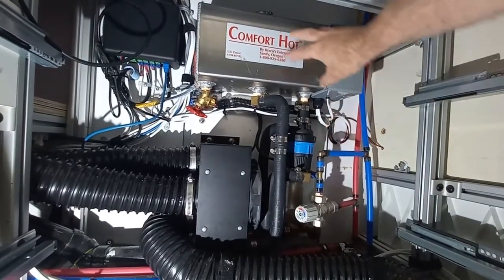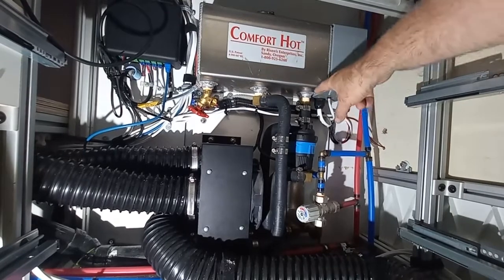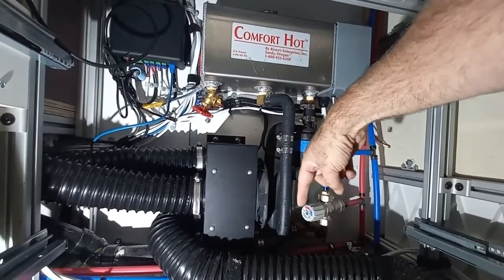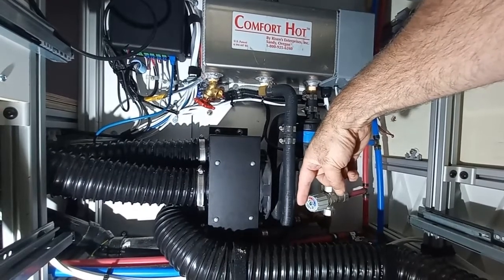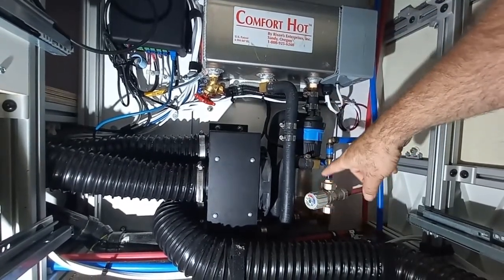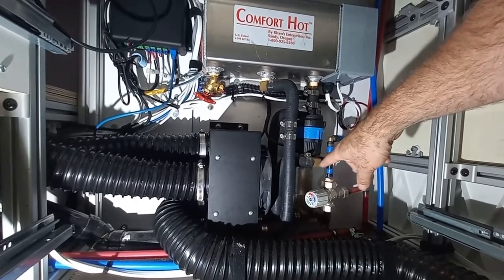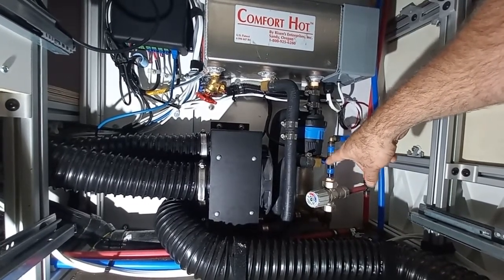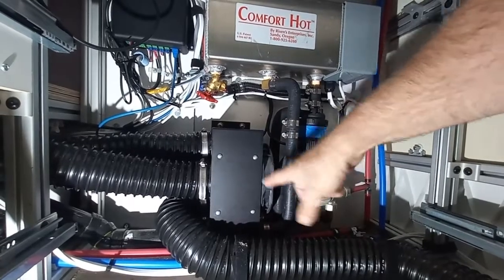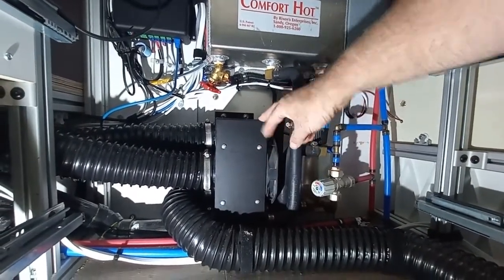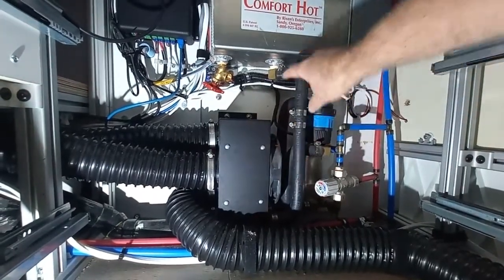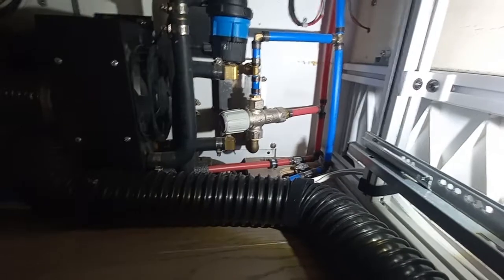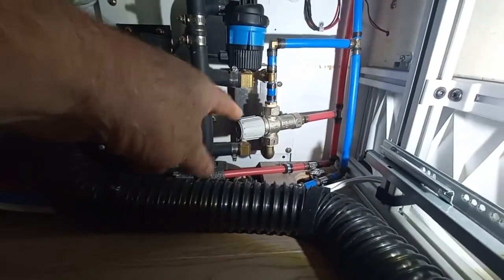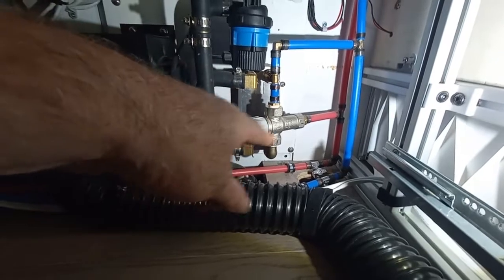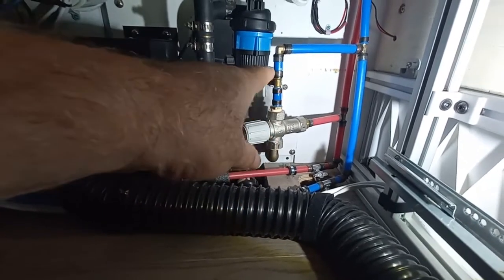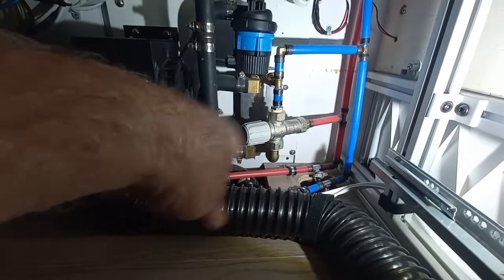If you're using the diesel heater, this tank eventually does get warm, but when it starts, it's pumping cool glycol down into the furnace, or the boiler, that sits down below. Hot glycol comes up into the water-to-water heat exchanger, which heats the hot water. Then the glycol travels into the back of the air exchanger, which heats the hot air, and then back up into the tank. In addition to the water-to-water heat exchanger, there's this mixing valve which takes the potentially really hot water and cools it down to usable hot water in the van.